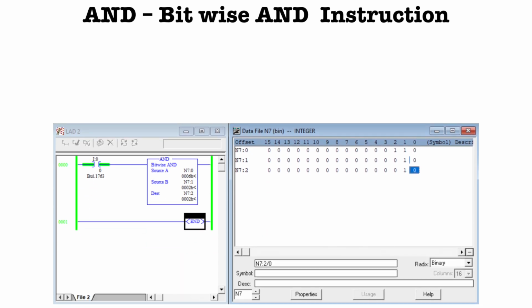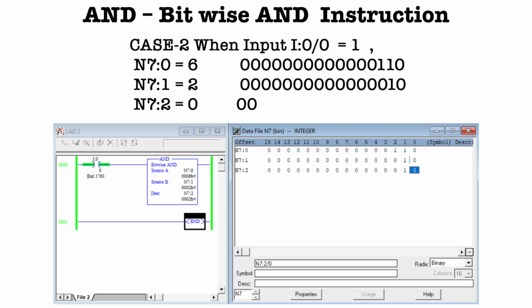So what happens here is, when I press the switch, it starts the bitwise AND operation and provides the result in the destination address. You can see in the diagram, when I press the switch I:0/0, the data files change by the bitwise AND operation, right? For the bitwise AND operation, you can see the first bit of N7:0 and N7:1 is 0 and 0. That's why, when AND gets a 0 input, the output of the AND gate is 0, right? Similarly, you can see the second bit is 1.